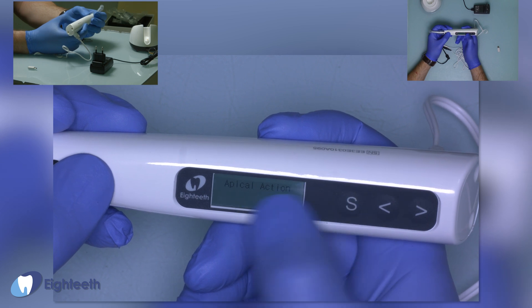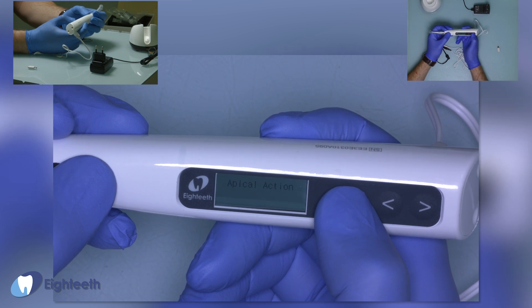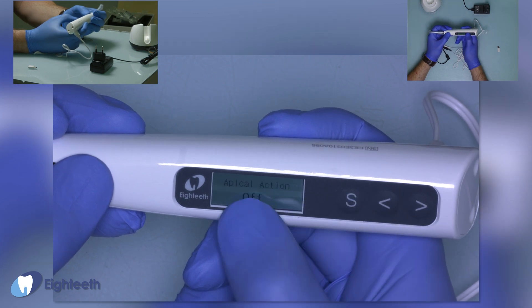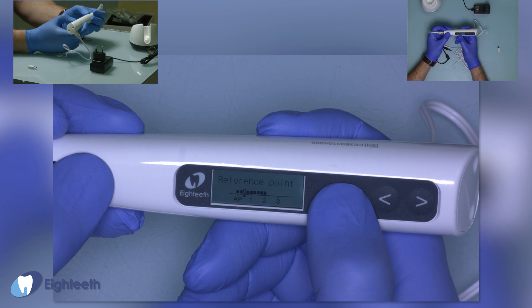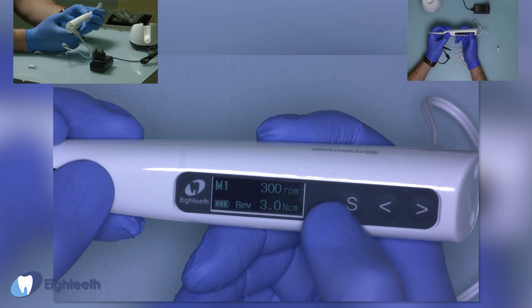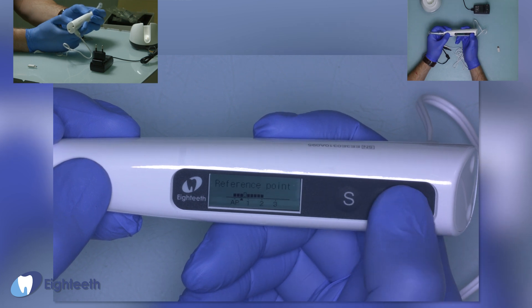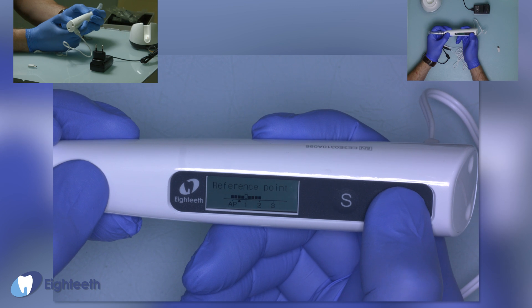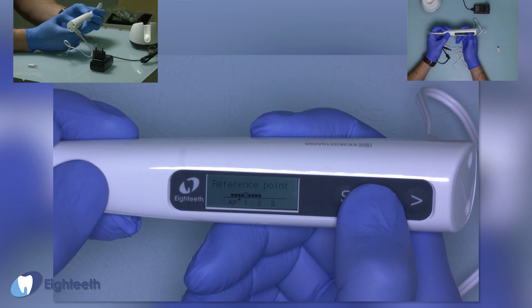There is also an apical action setting: when you reach the apical position, the motor can automatically reverse, slow down, or stop — or do nothing. You can set a reference point so that when you receive the alert that you have reached the apical position, it triggers before 2 millimeters, 1 millimeter, half a millimeter, or at zero position. Half a millimeter is good for getting information about reaching the root canal apical constriction.